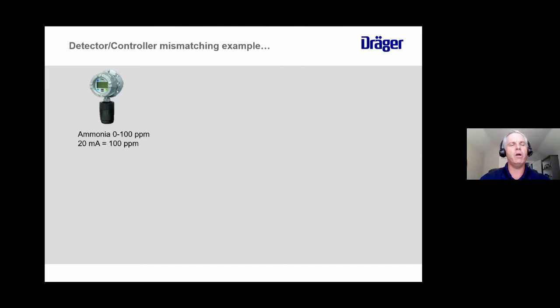So we talked on the last slide about detector-controller mismatching possibilities. This is how that could happen. Let's say you call Don Johns down in Mobile: Hey Don, I need an ammonia transmitter. He goes, okay, I sell Draeger and I love selling Draeger, so I'm going to sell you one of our Polytron 8100s with an ammonia sensor. And they say, well, we need that thing to be 0 to 100 ppm range. Oh yeah, no problem, you can do that. Just set the range at 100 ppm, you're good to go.